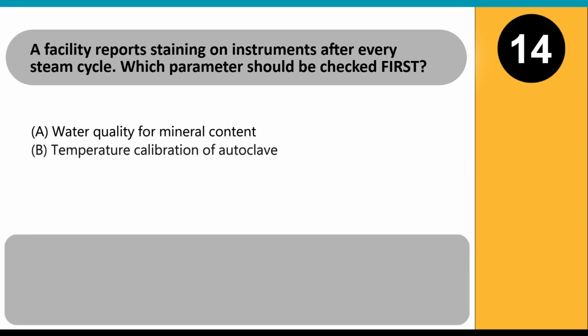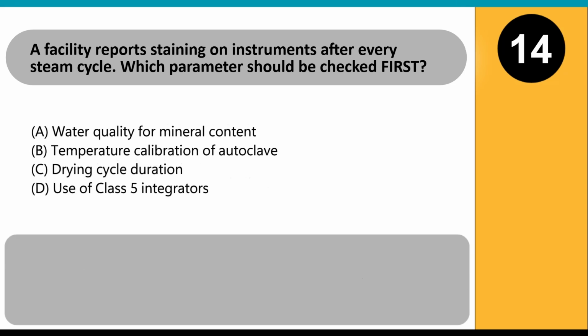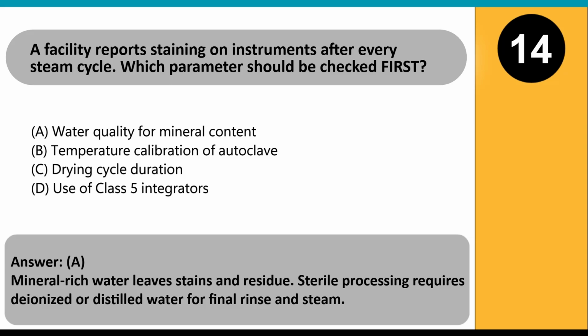A facility reports staining on instruments after every steam cycle. Which parameters should be checked first? A. Water quality for mineral content. B. Temperature calibration of autoclave. C. Drying cycle duration. D. Use of Class 5 integrators. Answer: A. Mineral-rich water leaves stains and residue. Sterile processing requires deionized or distilled water for final rinse and steam.